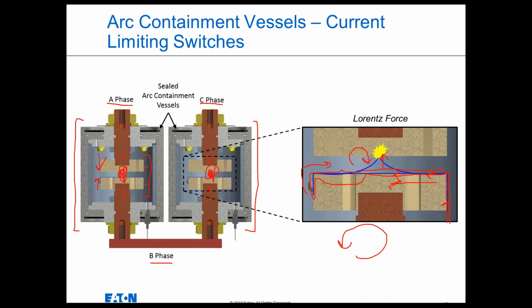And that standard says, among many other things, that the minimum distance between uninsulated power conductors in the switchgear is 1 inch. So that means inside UL 1558 switchgear, all of the power conductors that are uninsulated are 1 inch or greater apart. So by placing these two sets of contacts less than 1 inch apart, when we create an arc across them, we are guaranteed by the laws of physics that that current path will be lower impedance than any other possible current path in the switchgear, thanks to UL 1558 and that 1 inch minimum rule.